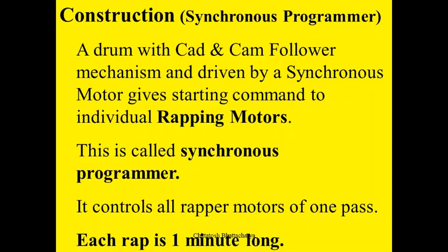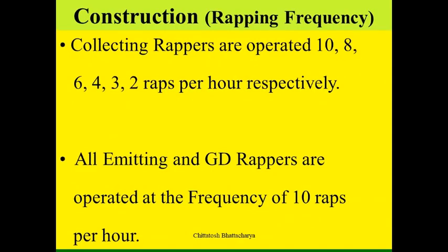For sequential rapping, a drum with a cam follower driven by a synchronous motor gives starting commands to individual rapping motors. This is called a synchronous programmer; it controls all the rapper motors of one pass. Each rap is one minute long. Collecting rappers are operated at a sequence of 10, 8, 6, 4, 3, 2 raps per hour respectively, while emitting rappers and gas distribution plate rappers are operated at a frequency of 10 raps per hour.